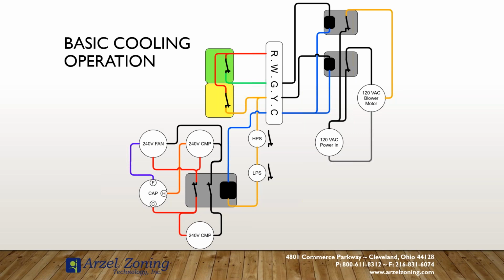And there's not a lot to it. You verify that your low voltage source is doing what it needs to do. And if you go outside and you see the contactor pulled in, you know your low voltage source is doing what it needs to do. If your stuff's not running, it's either a capacitor or there's no high voltage power. If it is running and they have a problem with cooling, you've got something else you've got to look at.